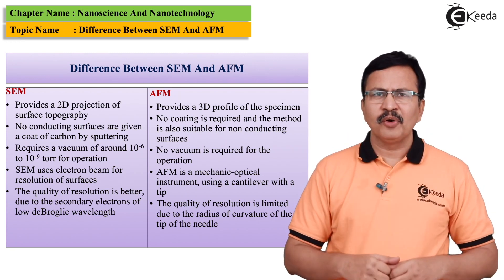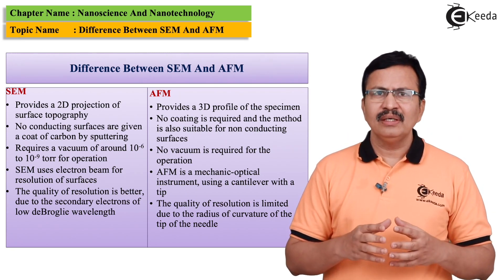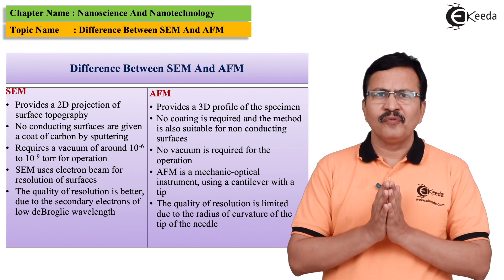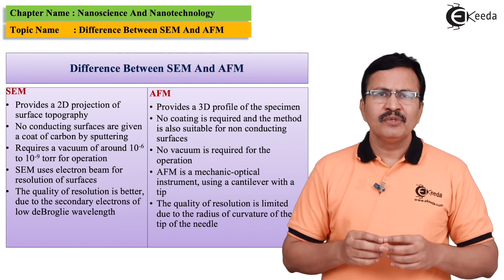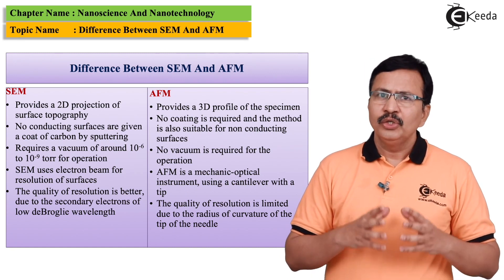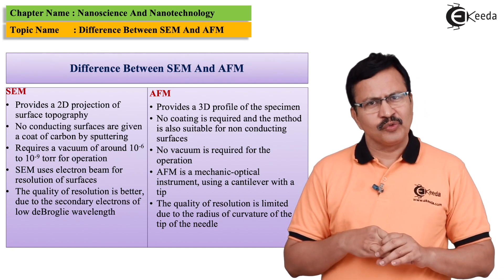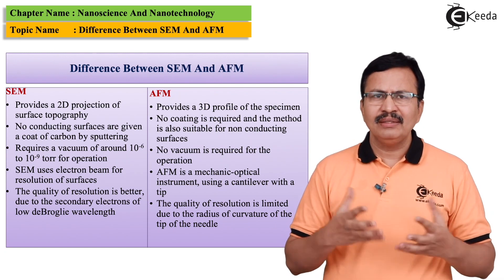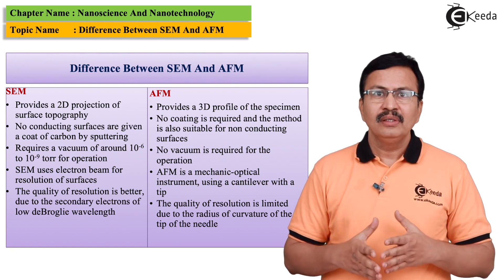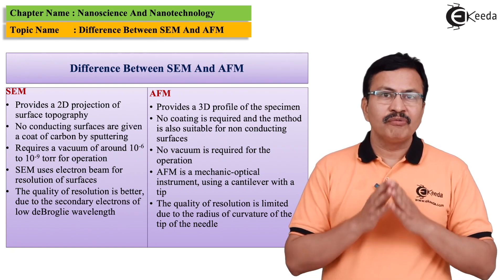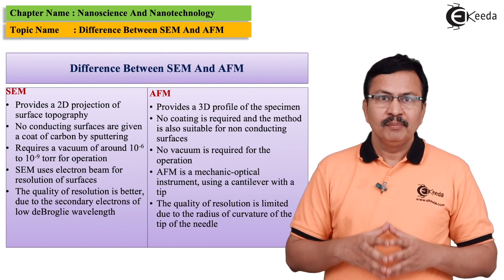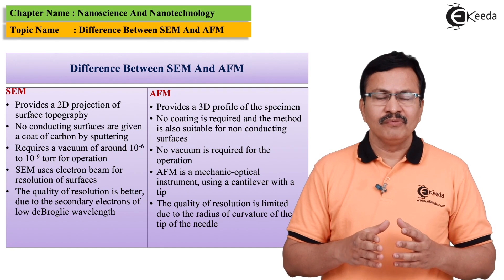A major disadvantage of SEM is that it requires a very high degree of vacuum, which is around 10⁻⁶ to 10⁻⁹ torr. As you know, the atmospheric pressure corresponds to 760 torr — so just imagine the low magnitude of 10⁻⁶ or 10⁻⁹ torr, because in SEM we use electrons.